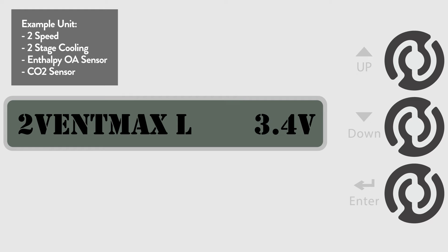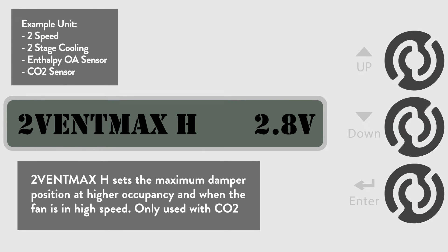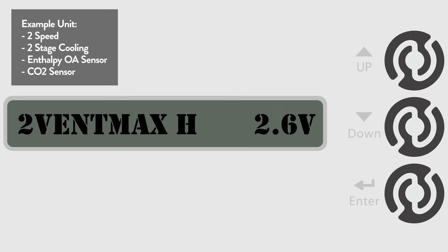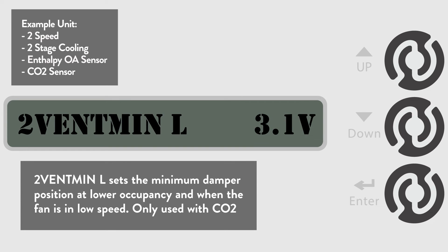Go to the 2 Vent Max H menu to set the CO2 sensor's maximum non-free cooling position when the unit is in high speed. The default is 2.8 volts, but we are going to change that to 2.6 volts. Now we will set the minimum outside air position when using a CO2 sensor. This would typically be for spaces with lower occupancy levels. Go to the 2 Vent Min L menu to set the CO2 sensor's minimum non-free cooling position when the unit is in low speed. The default is 3.1 volts, but we are going to change that to 2.9 volts.